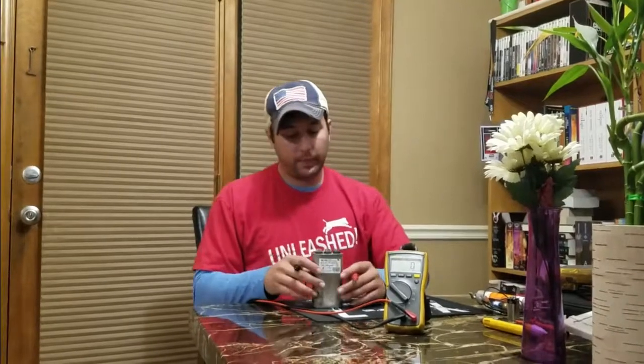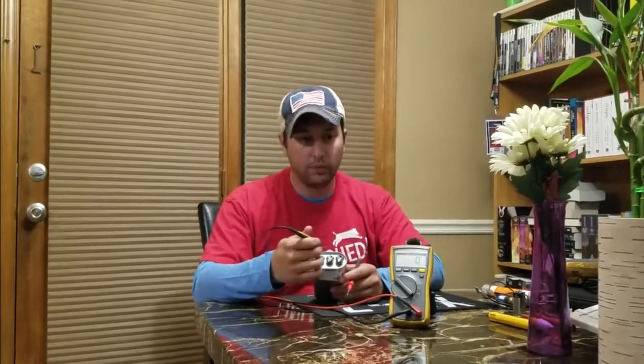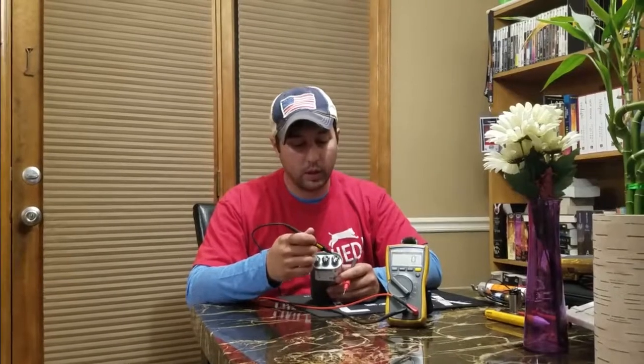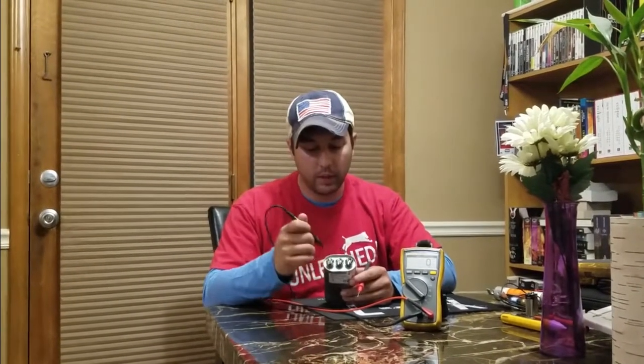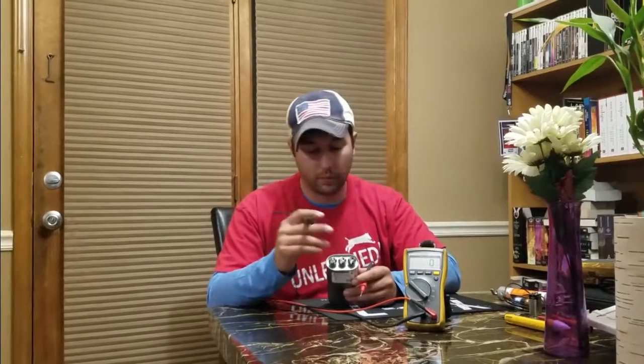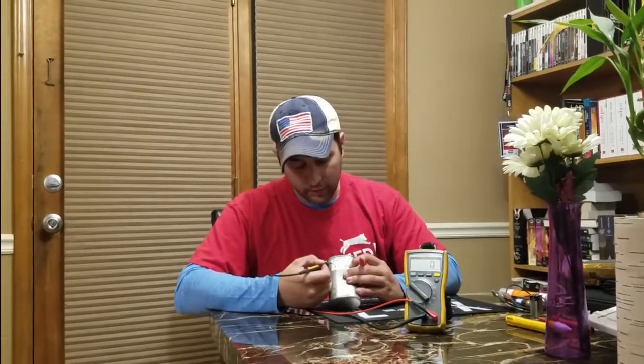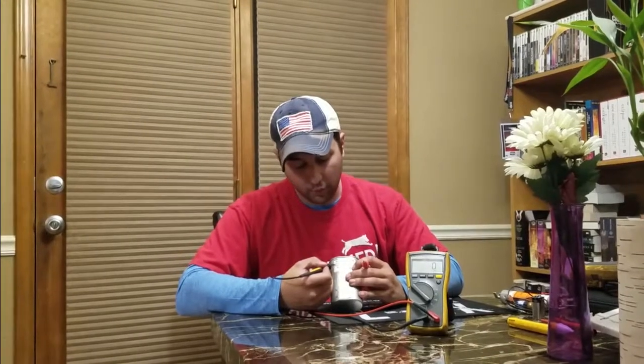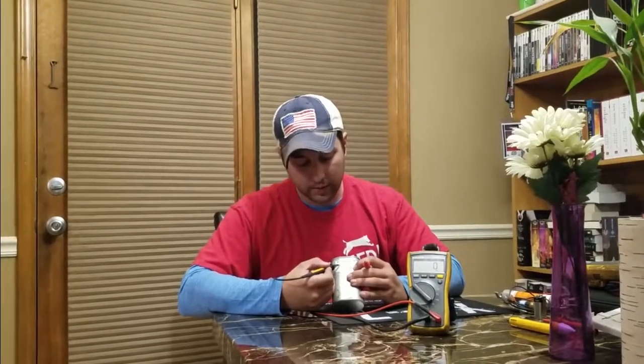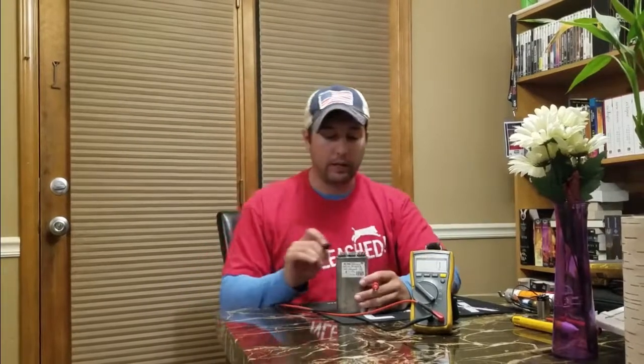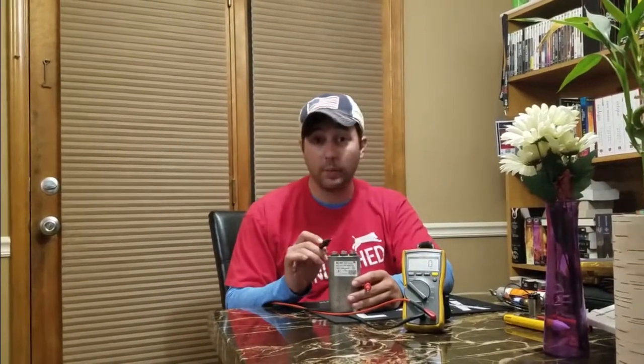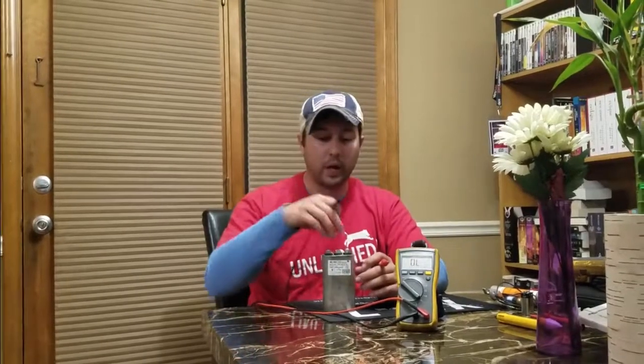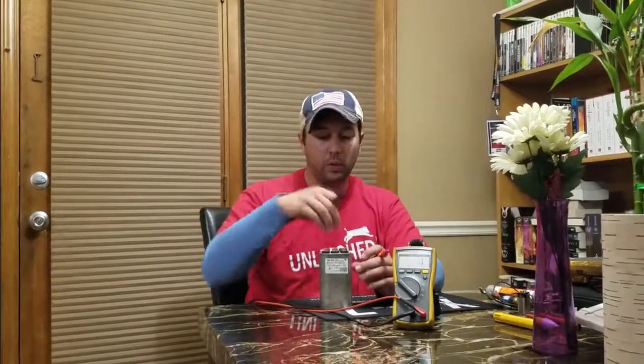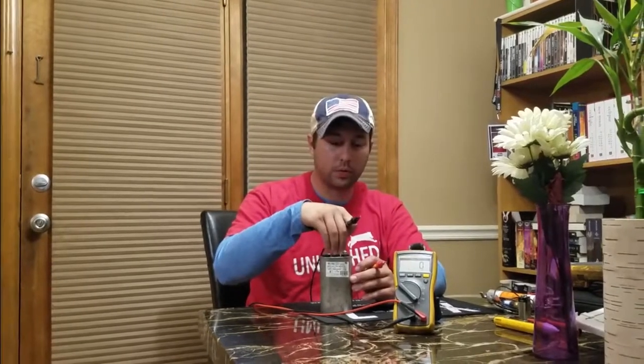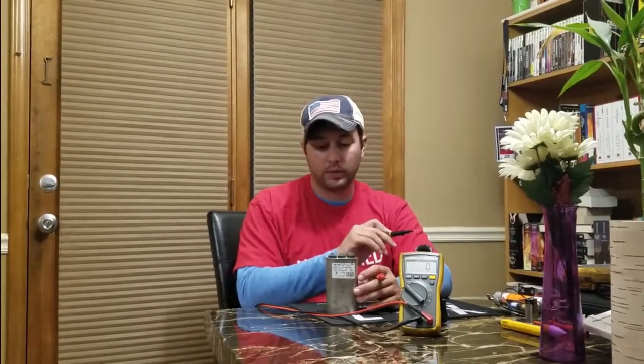On the top of this is a dual function capacitor. It works the compressor off of this terminal, and the condenser fan motor off of this terminal. If we look here, there are two different values — it's a little faded, but this is a 40 for my compressor side and a 7.5 for my fan side. This middle terminal is just a common hookup. We have a common power source come in here, one side goes out to our compressor, and one side goes out to our fan.